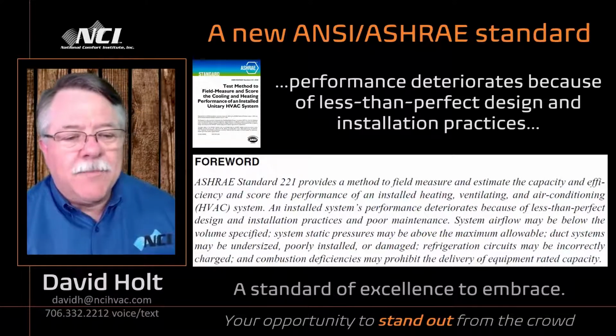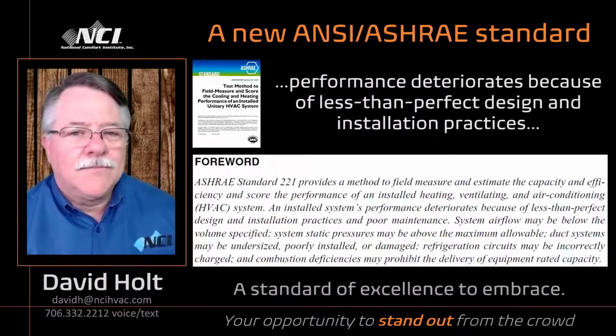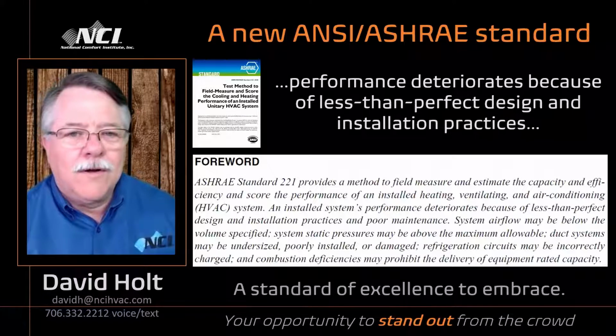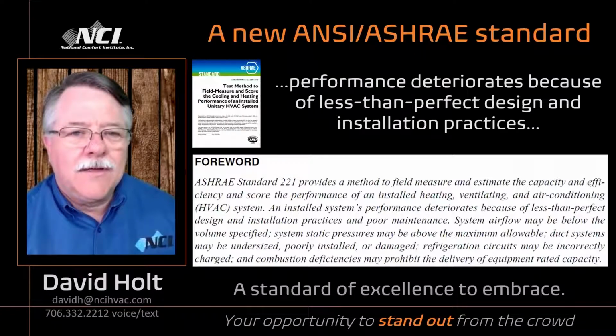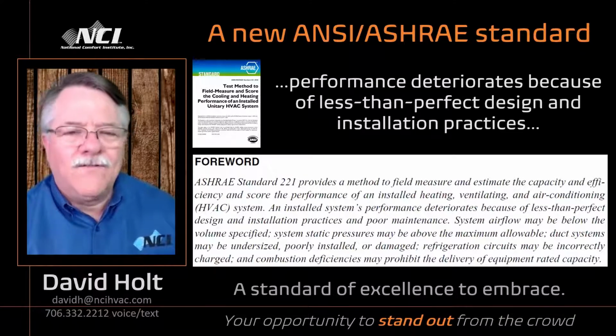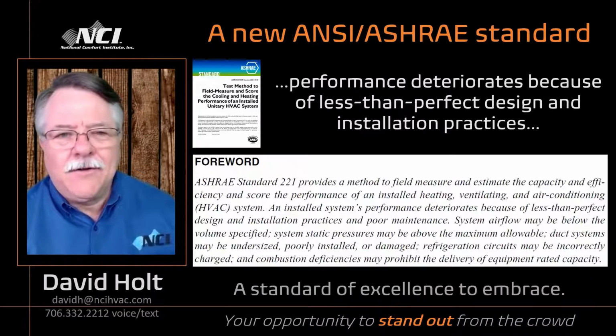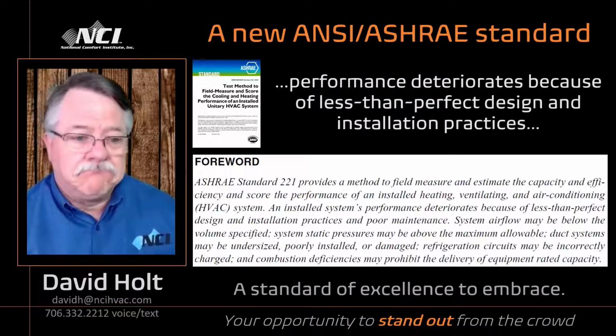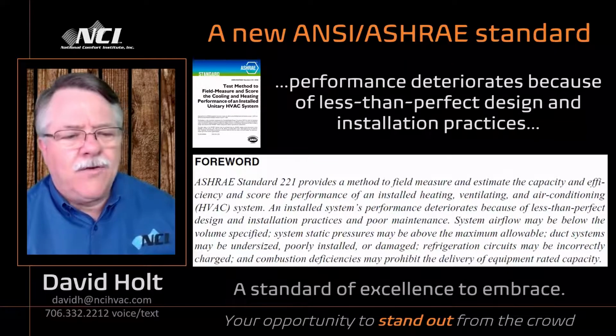System static pressures may be above the maximum allowable. Do you know that every blower installed by every manufacturer in our industry has a nameplate on there that says maximum external static pressure or something like that? And it says for most of them, 0.50, a half-inch water column. That's the measurement we use. You know that that's a standard for the equipment that we install, even if it's got a variable speed motor. So it may be running a little bit high.